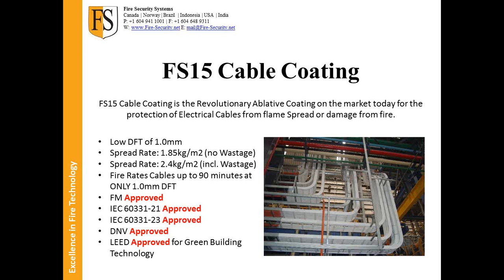Anything over that may heat the cable coating, and you do not want it to freeze, because once the water within the coating has frozen, then the coating's rendered useless. Okay. It can't defrost. It takes away the fire protection additives. Yeah, chances are not that big in Latin America. No, I don't think so. I think we have a heat issue, but not a frost issue. That's right. But we do have to be aware of that frost issue when we ship, because sitting in a 20-foot container outside of Hamburg on a ship may be -10 or -20 in winter, so we have to be aware of that situation of when we ship.